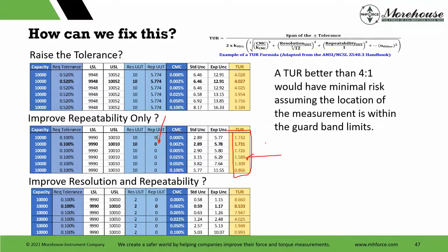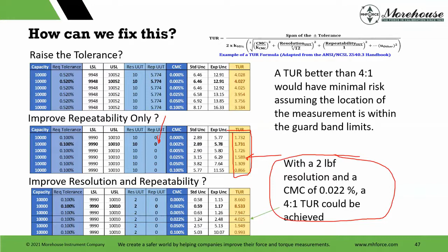And after they made it better, now we can back calculate, right? We can say, how good does that reference need to be to give us a 4-to-1? And what we came up with was a 2-pound resolution and a CMC of 0.022%, a 4-to-1. Again, that's not everybody's requirement. You don't always need 4-to-1, but if you want 4-to-1, this is a situation. That's how you're going to have to get it. You're going to have to severely modify the equipment.